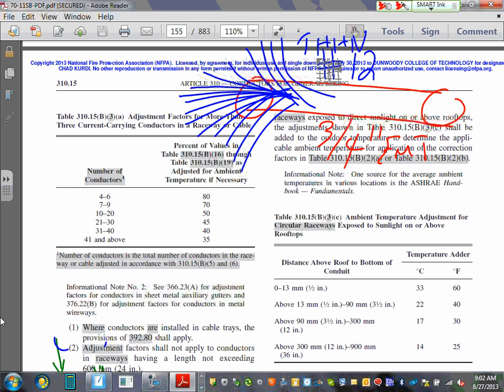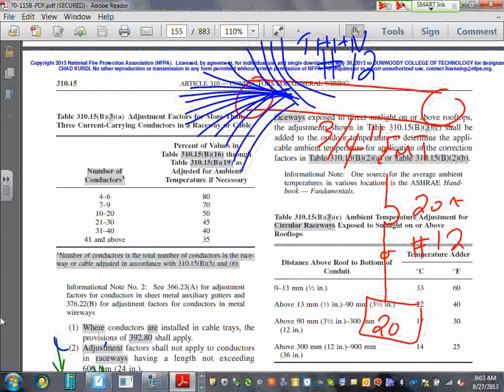under these circumstances, how much current, here's number 12, let's say normal operating condition. Normal operating condition is a 20 amp, here's number 12. How much current can you pull out of number 12, normal operating condition? 20 amps. If it's non-continuous, 20 amps. Can I pull other than 20 amps from number 12? No, because that's a small conductor.